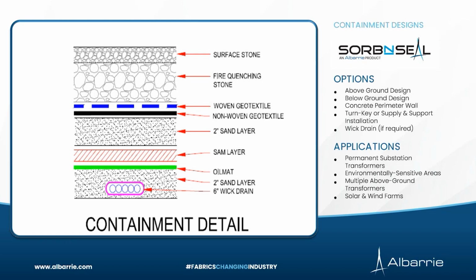This is a very popular design for all kinds of substations, in retrofit applications where you're trying to add containment afterwards so that the substation can meet today's environmental standards. In new installations, for larger equipment, it's more cost effective than a traditional concrete containment. For smaller equipment, it's still a pretty good option. The savings between large and small equipment might be a little smaller when compared with concrete. But if you look at the life cycle value compared to a traditional concrete pit, in the long run this is a much better value.